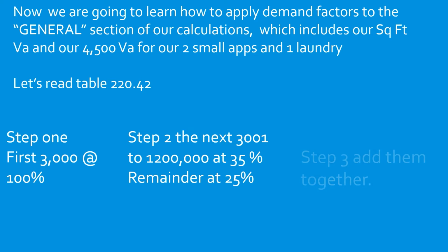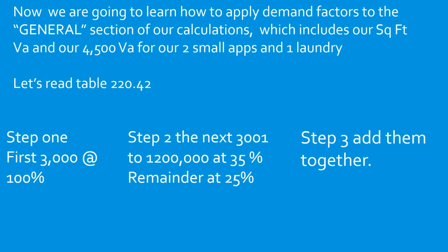So step 3, we're going to add them back together. Step 1, we take the first 3,000 VAs at 100%. Step 2, we take the next 3,001 up to 120,000 at 35%. And then step 3, we just add those two numbers back together, and that gives us our total VAs for the general section of our load calculation. It may sound overwhelming now, but I'm confident in you, and I believe that once we work through this, you're going to be a pro at it.